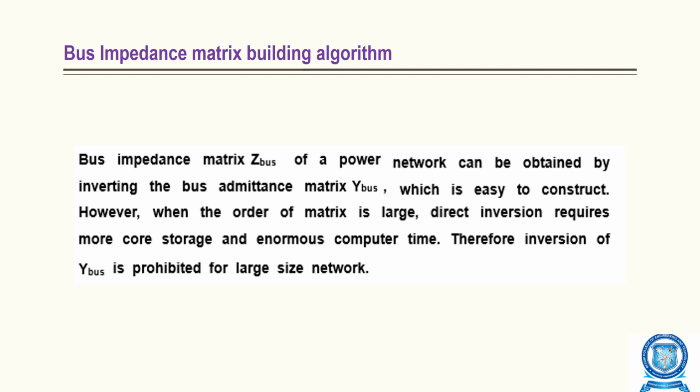In the previous session, we discussed the impedance matrix by Thevenin's equivalent circuit. The reduction of a network to find the value of Thevenin's impedance is difficult for a complex network with a large number of branches. The Thevenin's impedance can be obtained from the Z-bus matrix. The Z-bus matrix can be obtained by taking the inverse of the Y-bus matrix, but normally it is obtained by using the Z-bus building algorithm. The step-by-step procedure to determine the Z-bus matrix is explained in the following session, by using the building algorithm.